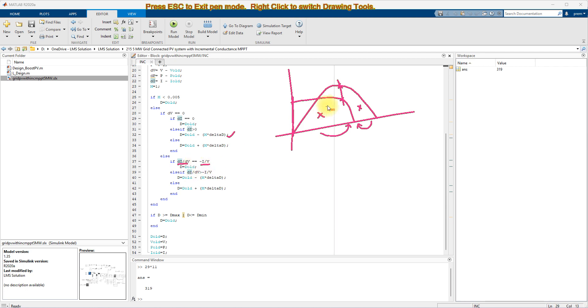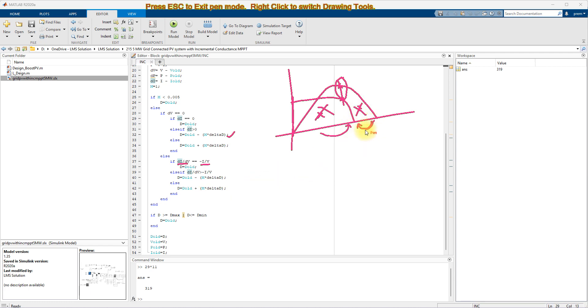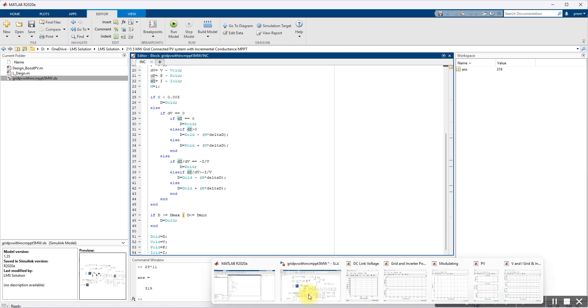If dI/dV equals minus I/V, the system is at the maximum power point and no duty cycle change is needed. If dI/dV is greater than minus I/V, we need to decrement the duty cycle to increase the PV voltage. If dI/dV is less than minus I/V, we need to increment the duty cycle to reduce the PV voltage and bring it back to the maximum power point. This is the working principle of the incremental conductance MPPT, implemented as code to generate the duty cycle.